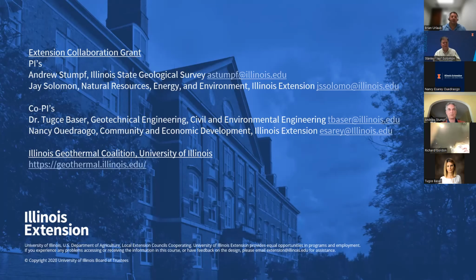If you don't have any of those opportunities, it becomes a hybrid system where we use some type of fluid cooler or cooling tower, designed a couple different ways depending on location. What we try to do is downsize that equipment and use it more as a pre-cooling device, running it at night when the ambient temperature is cooler than the ground, or in the spring to bring the ground back to its natural temperature rather than letting heat build up year over year. Alternatively, you can size it strictly as a peaking system, turning the device on only once you hit a certain temperature for peak shaving.